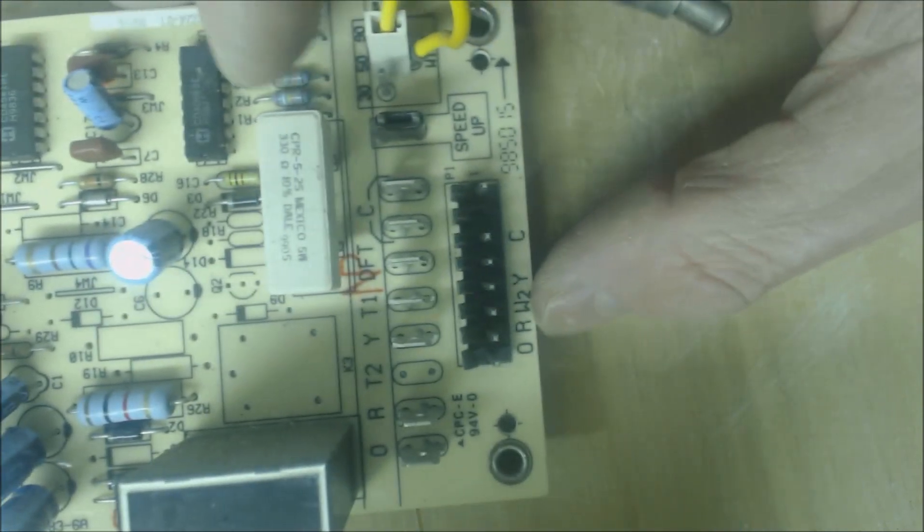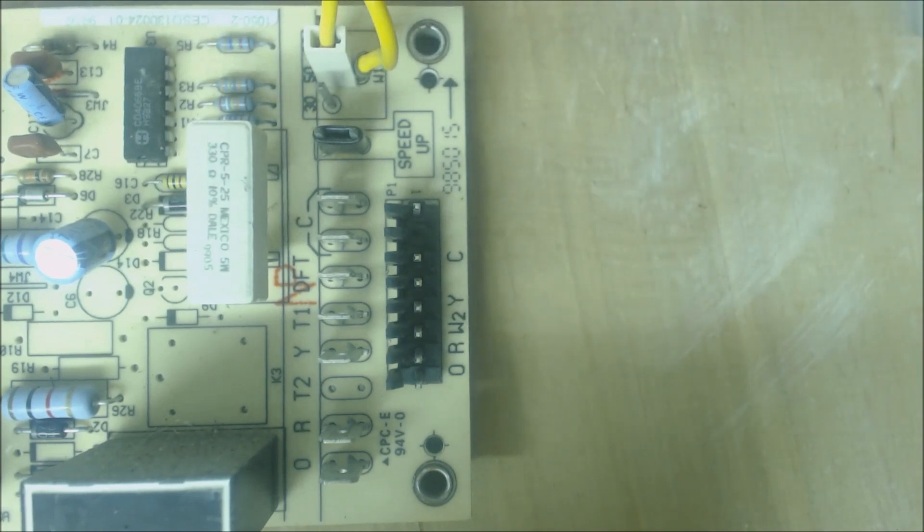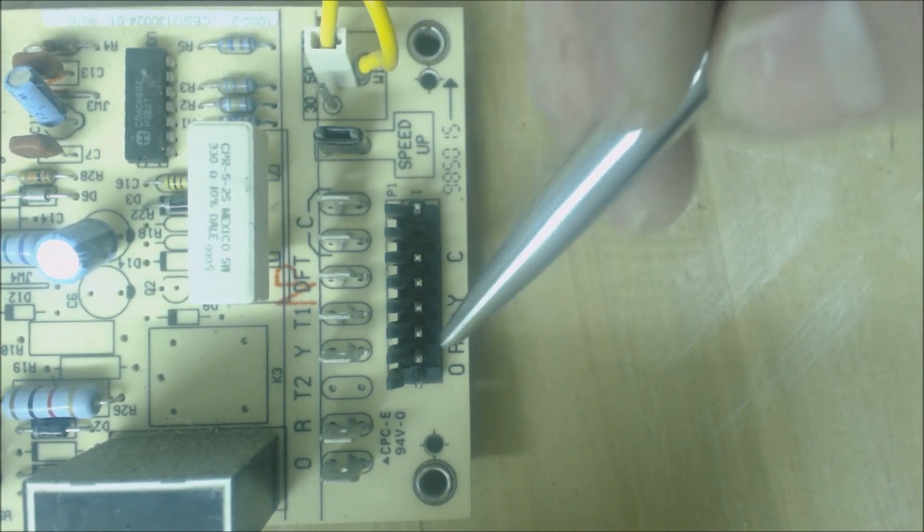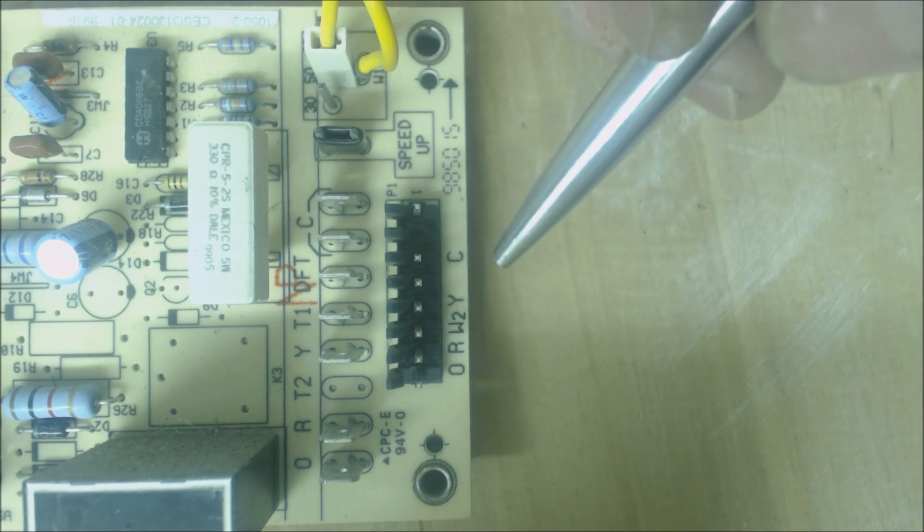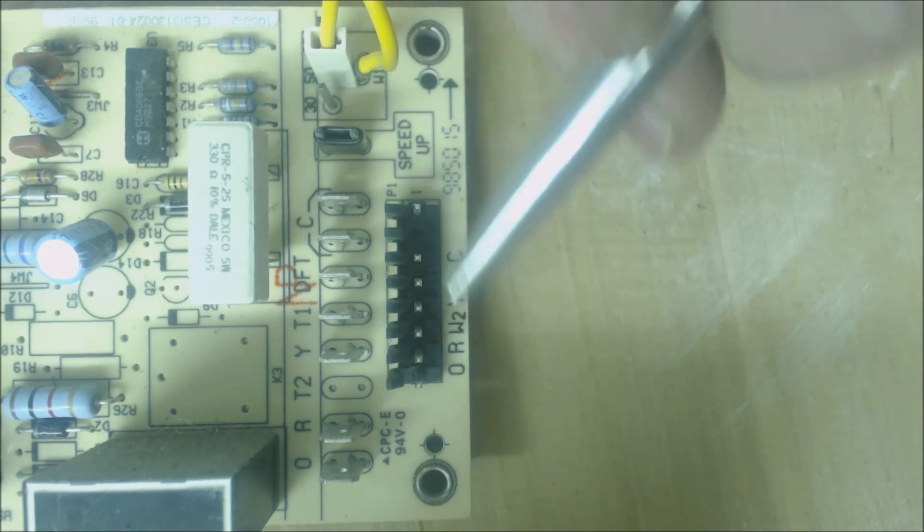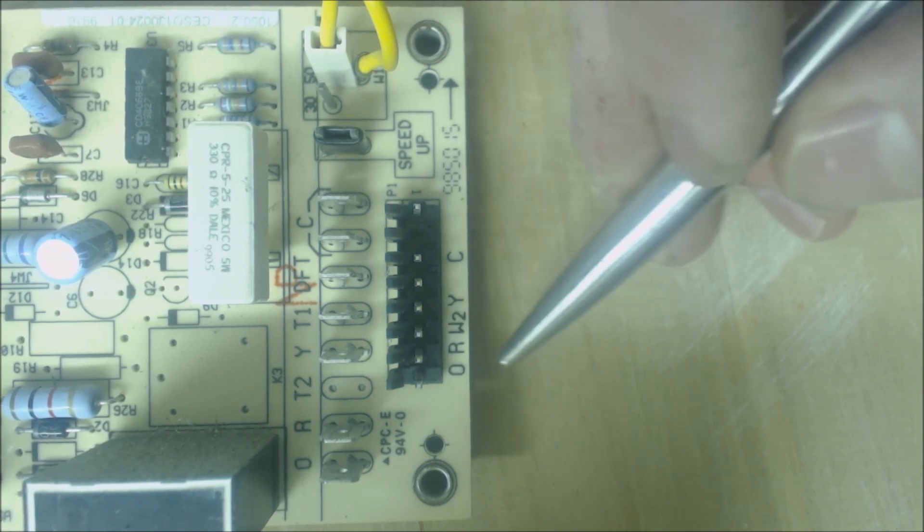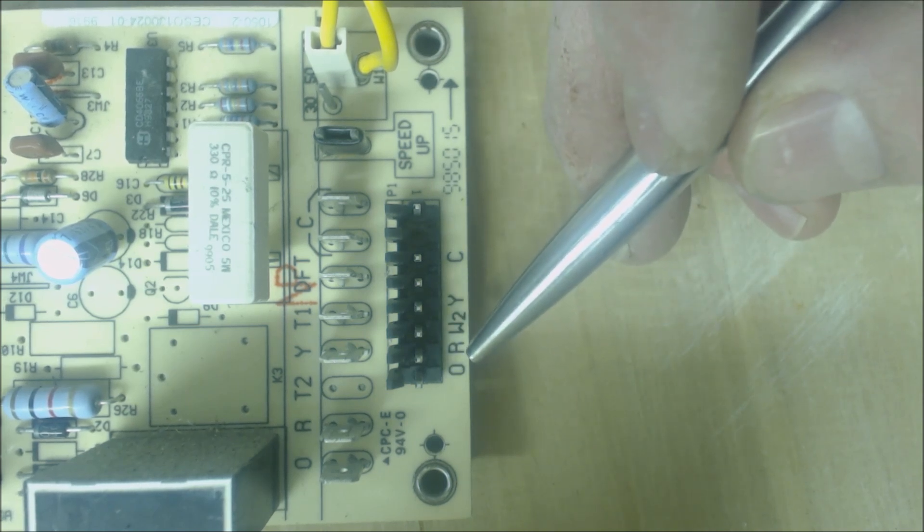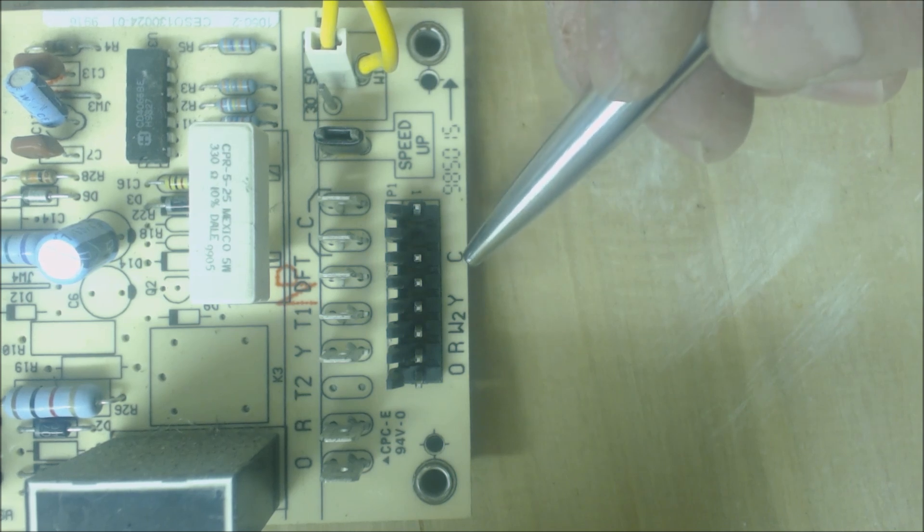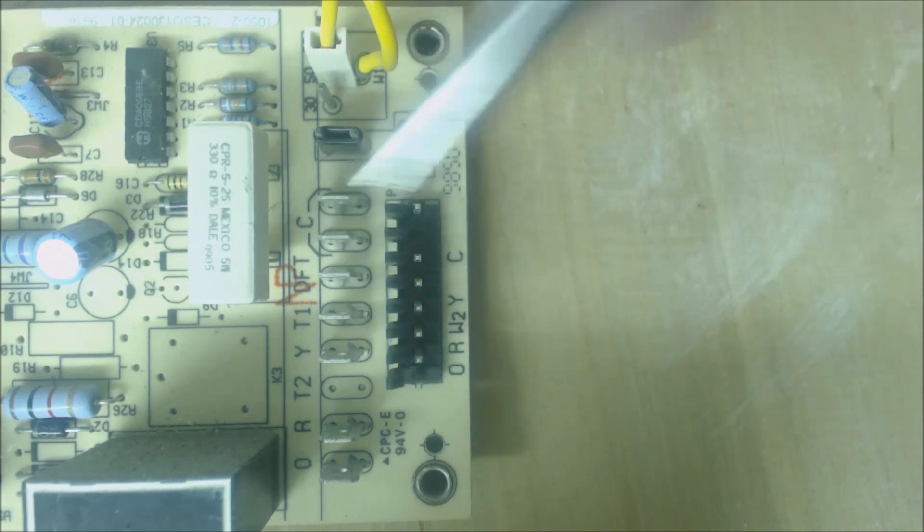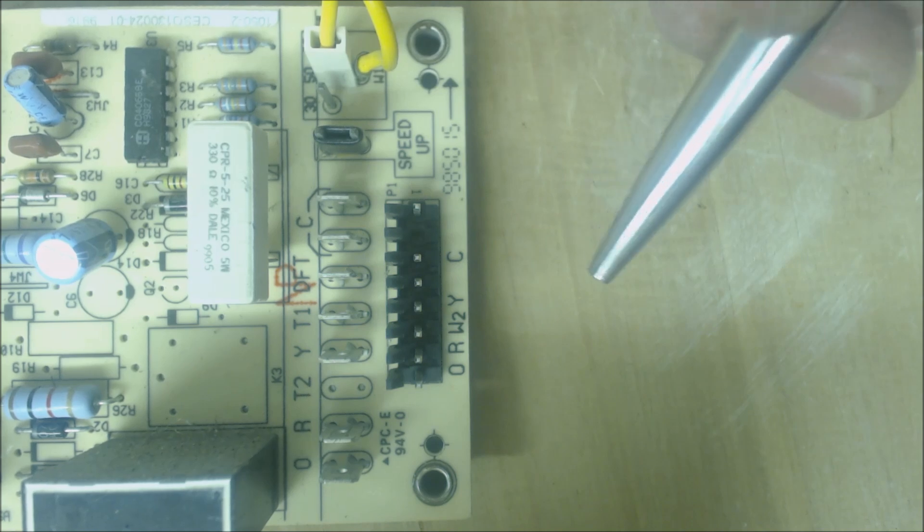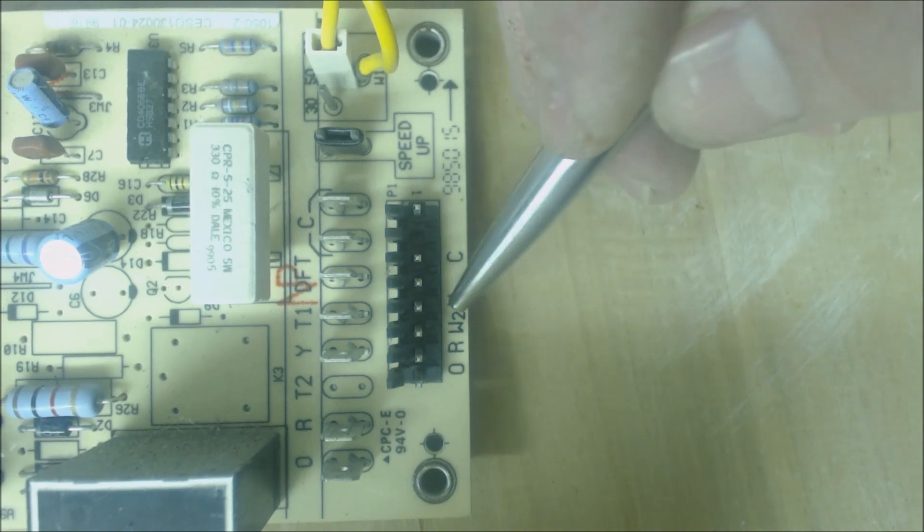We'll start with our low voltage thermostat wire connections coming in. There's a wiring harness here, and you wire nut the thermostat wires onto the individual wires on the harness. R is 24 volt power coming in, and common is the path back. That's what powers the defrost control board. Y is 24 volts coming in powering the compressor.